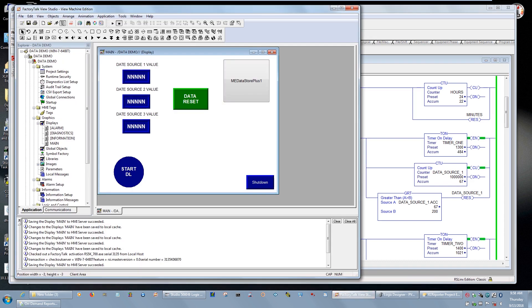I already previously set up Factory Talk View Machine Edition — I'm using version 10 — where I have three different viewpoints of the display object for accumulation of the timers, a data reset that will reset all the values, and a starting data log button that writes a 1 to wipe out and reset values. I also have the Machine Edition Data Store Plus object, which runs through ActiveX on the computer. Any PanelView Plus version 6.10 or later can run this, but I strongly recommend version 10 because it includes features like audit trail to a CSV file to comply with 21 CFR Part 11.